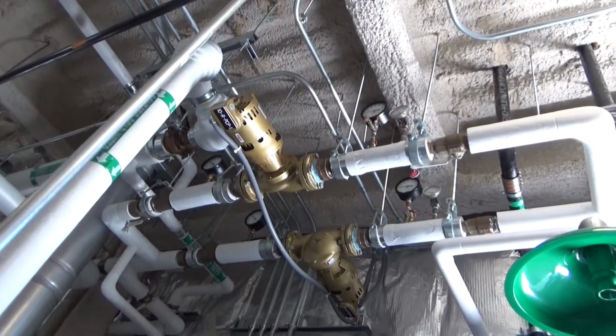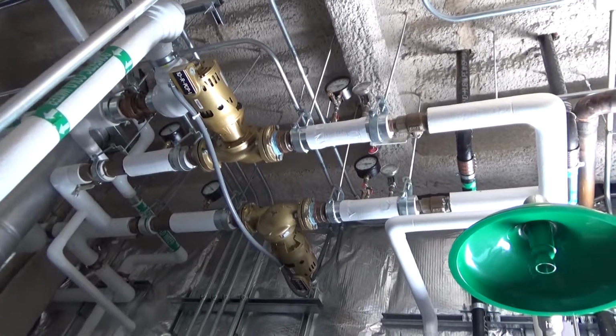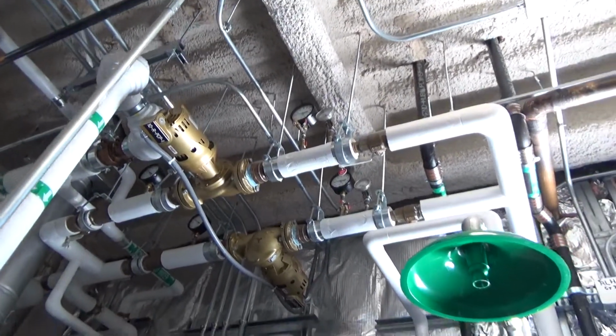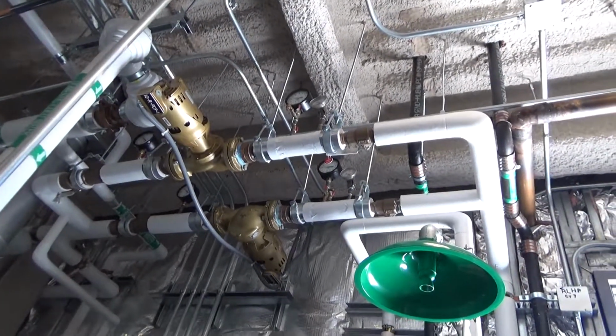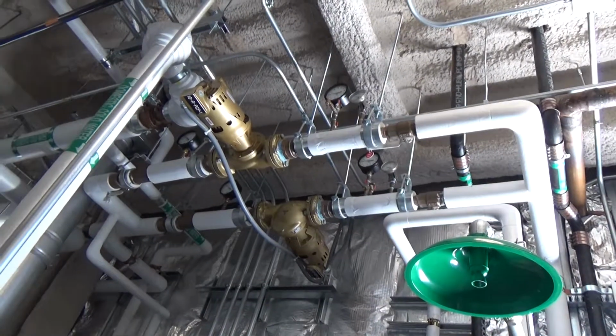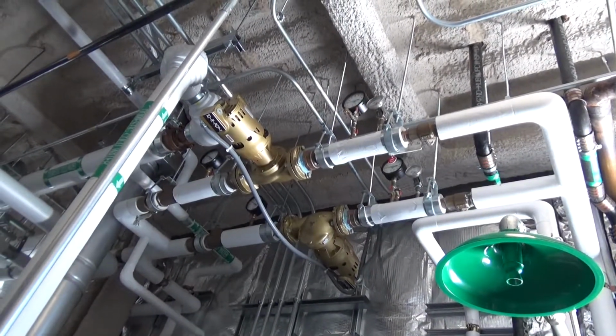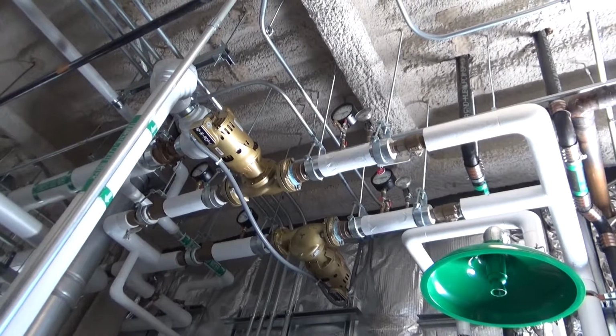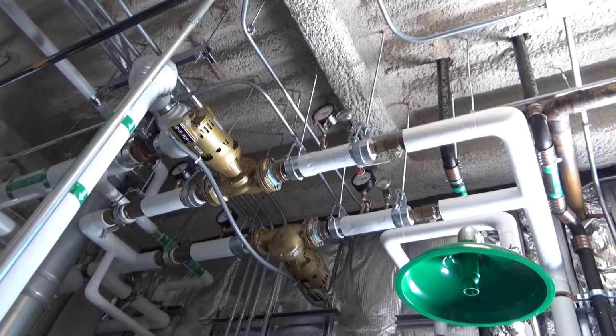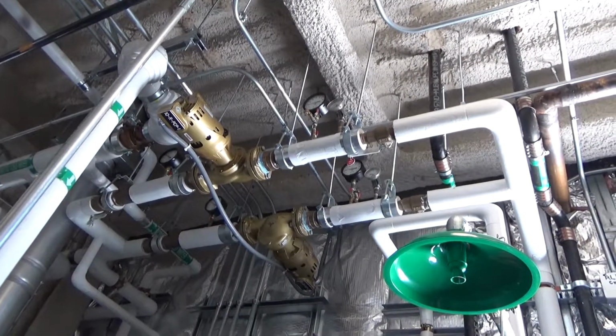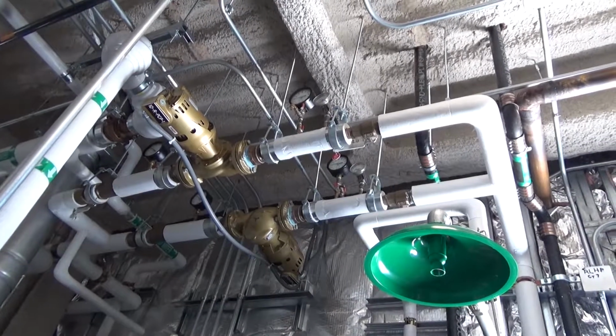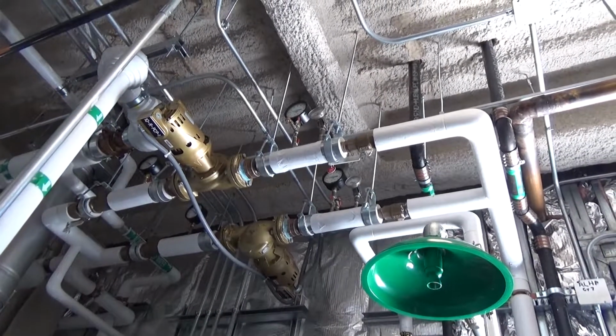Wait 2 years, and that differential starts to change and gets lower. It's probably getting clogged up. Then you probably are starting to get debris in there, and it's probably time to pull it. So just remember your delta across there, your delta P, and record it. If you start getting less of a delta, things are starting to get clogged up. So on that, there's no maintenance.